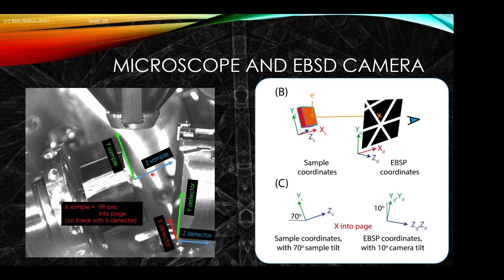The conventions we use: Z points out of the sample, the 2D map is orthogonal at right angles for X and Y, and X Y Z form a right-handed set. We describe that indexing happens with respect to a reference crystal in the diffraction pattern. We want to relate this to how the beam is scanned across the sample. A relatively simple case to do is to rotate the sample about the Z axis, doing an in-plane rotation of our crystal, which should result in a rotation across our diffraction pattern.